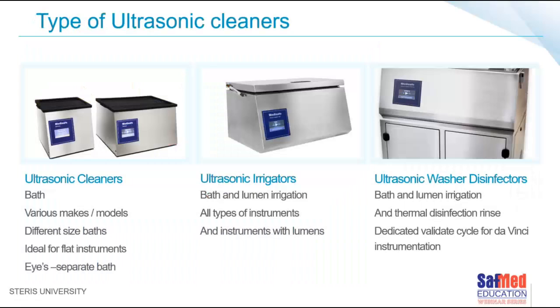We get different types of ultrasonic cleaners. We get ultrasonic baths, obviously various makes and models and different sizes and volumes depending on what it is you need. They're absolutely ideal for flat instruments and instruments that don't have any lumen flush. You open the lid and put your instruments inside and they clean the outside of the instrument really, really well. They will get into some nooks and crannies, but not necessarily irrigate lumens. Absolutely ideal for eye instruments. We use smaller baths generally for eye instruments, and we prefer, of course, to use a separate ultrasonic cleaner for eye instruments.